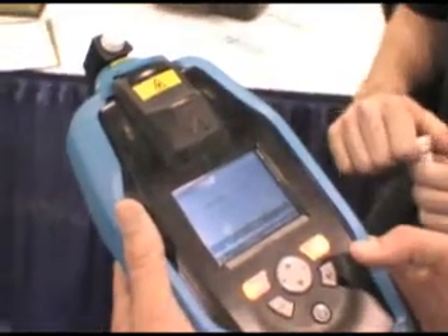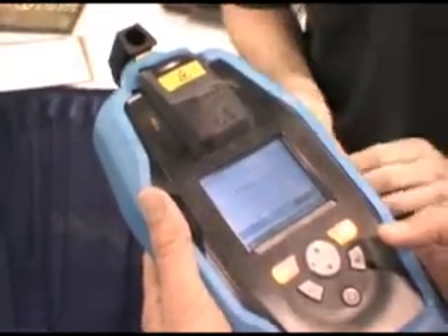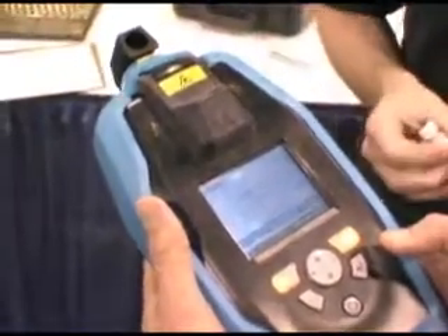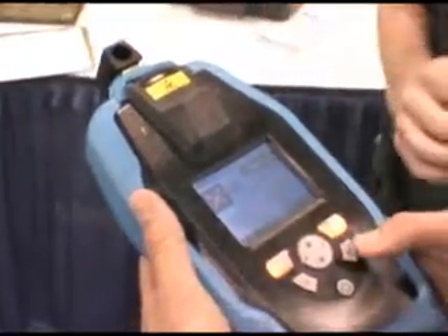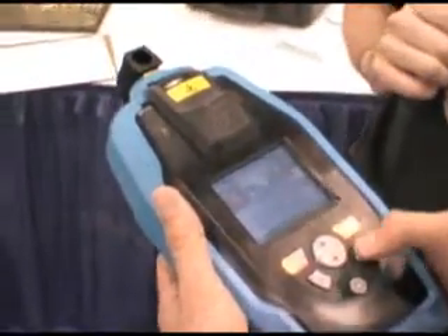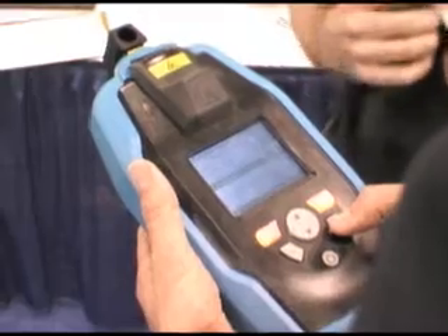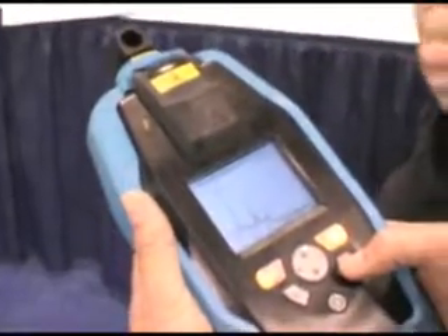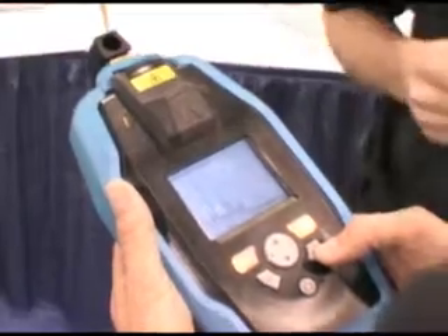We've failed. Let's go down to discover. Hit the down arrow and hit enter — it says acetaminophen. Acetaminophen clearly is not cyclohexane. People like to see the spectrum, to see how rich that particular scan was. They can take this spectrum — this fingerprint — offline and put it into a report: why did it fail? Was it the wrong drum? Did the operator scan the wrong instrument? We're trying to quickly resolve identity.